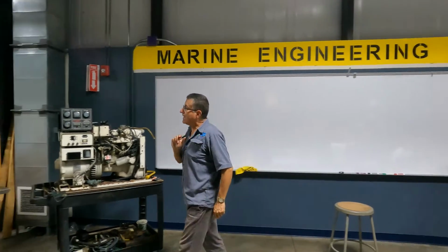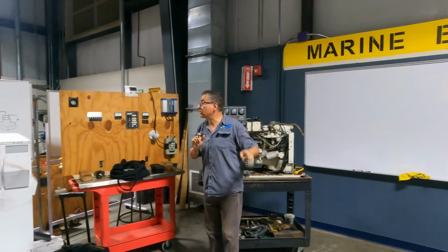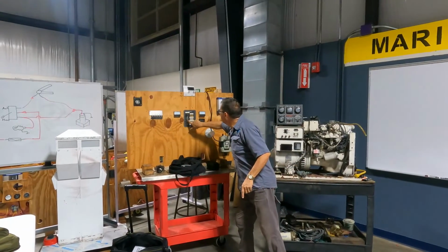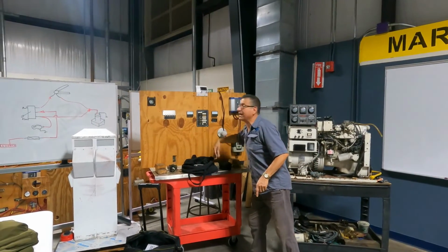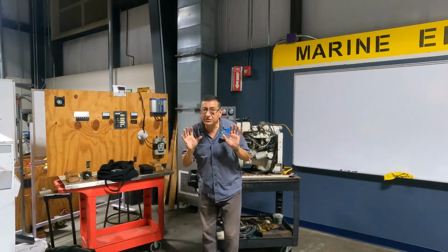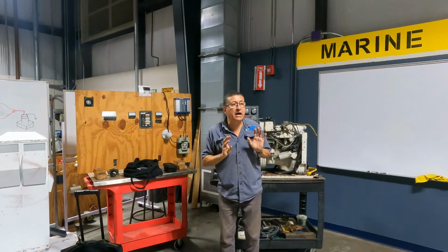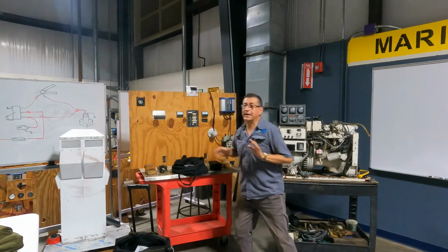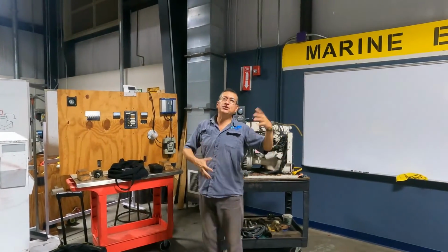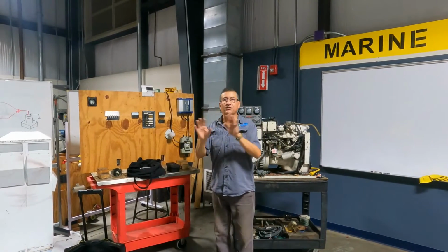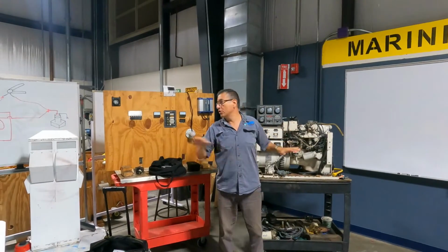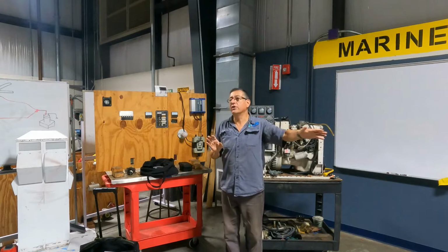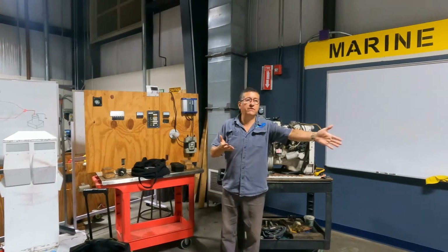But I am going to use, when the inverter is running, only this and this. The other breakers, no, because it's an emergency, only to 2 hours or 3 hours, only those lights, refrigerator, and that's it. No, I need air condition and jacuzzi. No. Air condition jacuzzi is with this or this. No jacuzzi with inverter. No sauna with inverter.